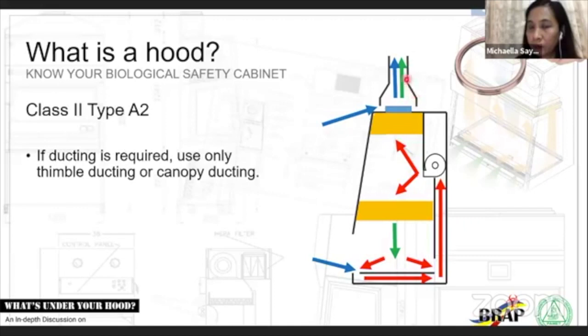So in this illustration, you can see this is not attached to your A2 cabinet. There is a space here, just enough for your exhaust system to suck in room air and exhaust it out. Not so much so as to put additional pressure to your biosafety cabinet. So this has to be balanced. Your exhaust duct should be balanced with the exhaust system of your biosafety cabinet and the supply of your room. It is good to have a negative pressure in your room. However, if you have too much negative pressure in your room, you will generate several problems. So one, too much negative pressure may cause your ceiling to fall down. Imagine if you're sucking on your Zesto juice and you suck out all the air. What happens to your Zesto juice? It crumbles inside, implodes. That's a similar way. So that's the importance of balancing out your exhaust air here with your supply air in the room. Okay.